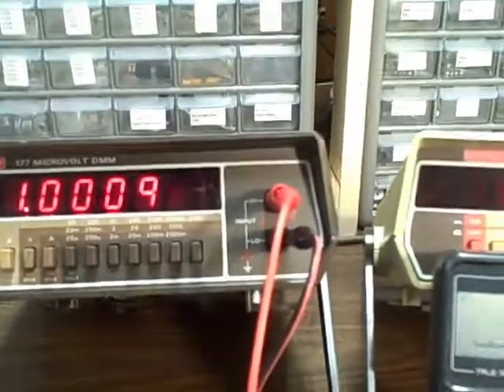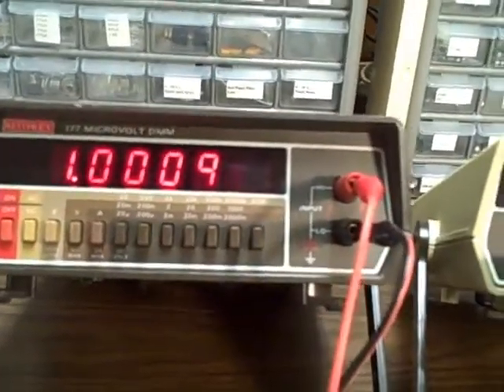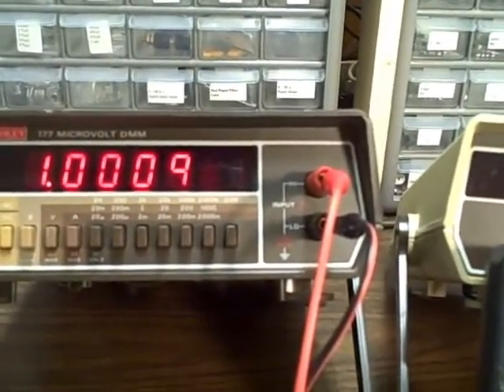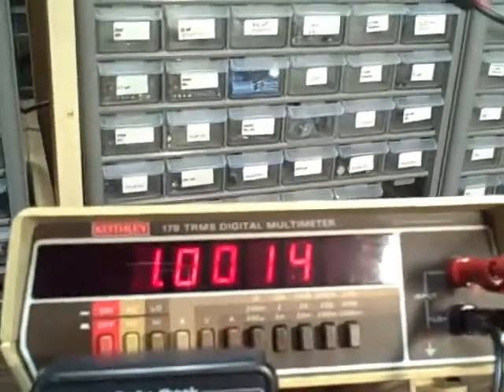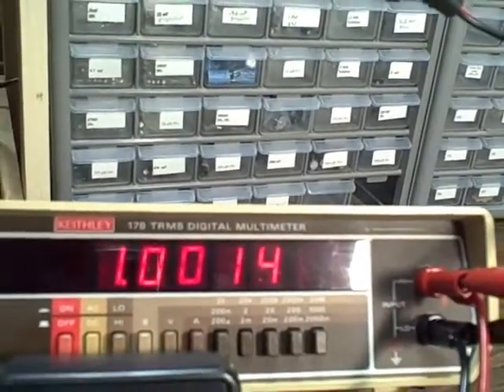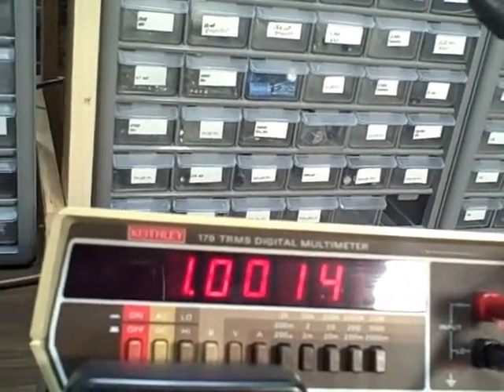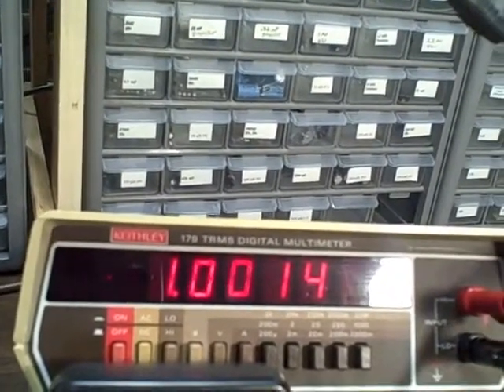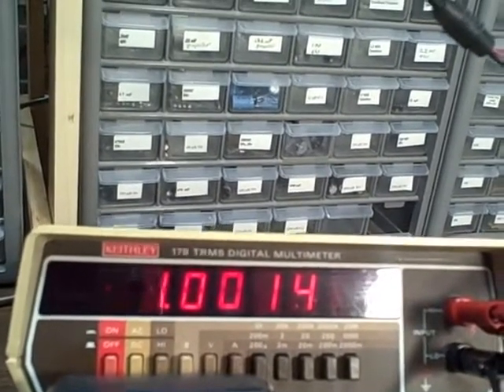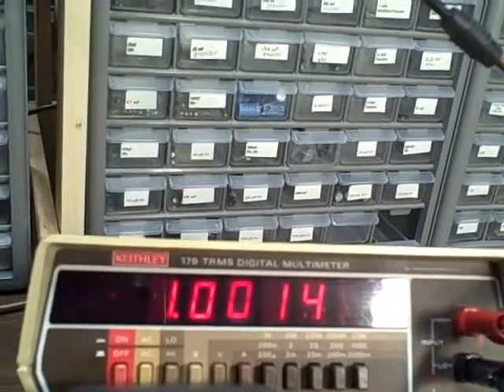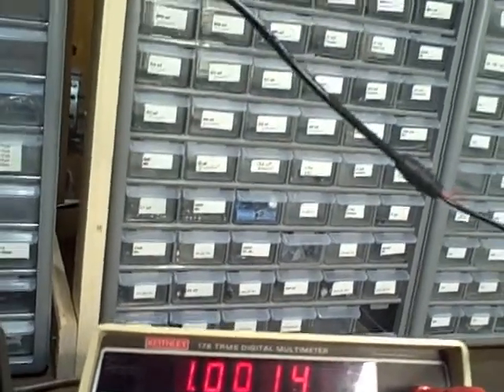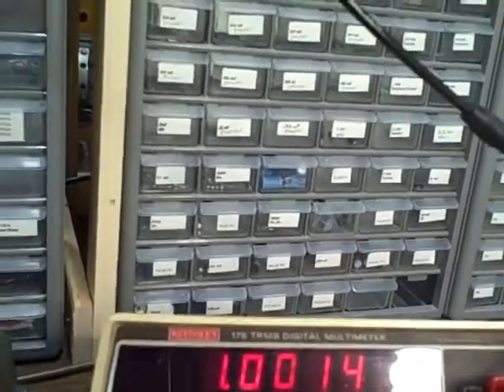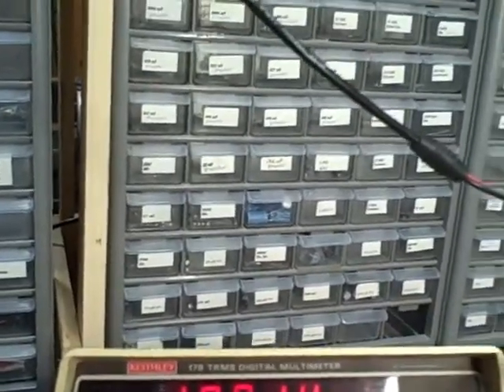All right. 1.0009 on the 177, 1.0014 on the 179. So approximately 0.4 millivolts difference, maybe 0.5 millivolts different. It's not a millivolt. 0.5 millivolts, yeah, that'd be right. So half of a millivolt different in AC at this end of the range.